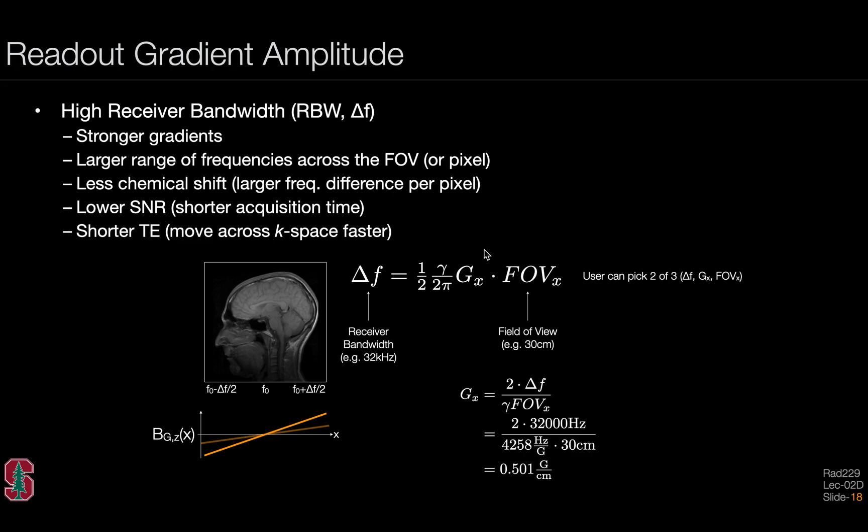This is done behind the scenes by the scanner. So we can rearrange this expression. And if we chose a field of view of 30 centimeters and we choose a receiver bandwidth of 32 kilohertz, then we see that we need to apply a half gauss per centimeter of gradient amplitude.